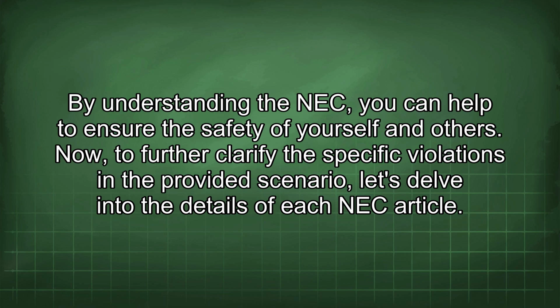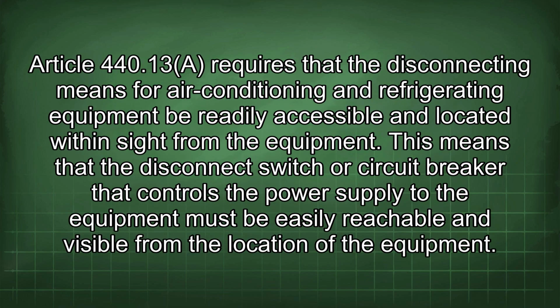Now, to further clarify the specific violations in the provided scenario, let's delve into the details of each NEC article. Article 440.13 requires that the disconnecting means for air conditioning and refrigerating equipment be readily accessible and located within sight from the equipment. This means that the disconnect switch or circuit breaker that controls the power supply to the equipment must be easily reachable and visible from the location of the equipment.